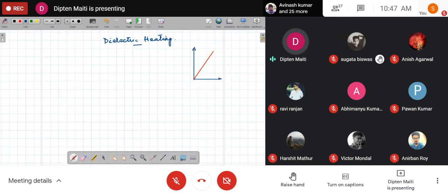Let's say voltage is applied across a capacitance. So due to that, the current passed through the capacitance is I. And this is a lossy capacitance. So the current would have two components. One is the IC, which is perpendicular, orthogonal to the direction of the voltage, and another producing the loss, that is the IR component. So for a lossy capacitance, of course, this is the power factor angle.